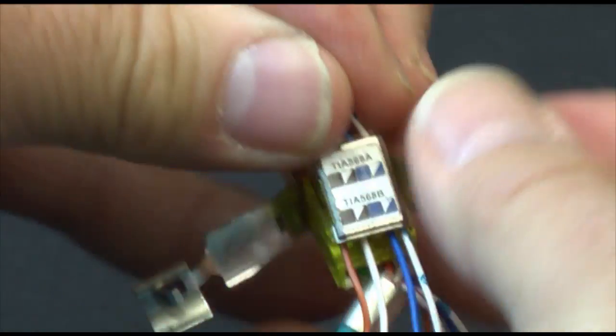Use your snips to cut the conductors on an angle from right to left, leaving each conductor to the left a little longer. Then open the small door, start to insert the conductors by color code, inserting the longest conductor, the brown one, into the hole to the left, followed by the second conductor and then the third and fourth sequentially through the color coded holes.